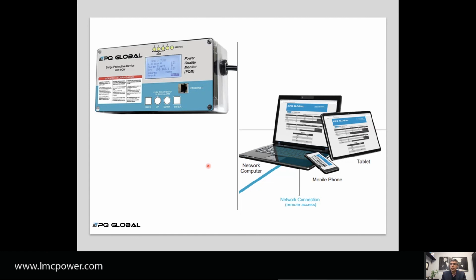We've seen a lot of equipment designed to measure these power quality problems get damaged — whenever there's a problem, you go to check and the meter itself is damaged. So having a surge protector within the meter not only protects our power quality meter, but also protects everything else connected to that panel. So we're providing multiple levels of service that other people cannot provide. This is called a PQM.